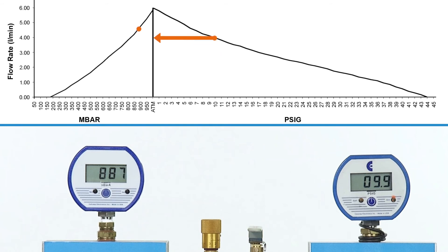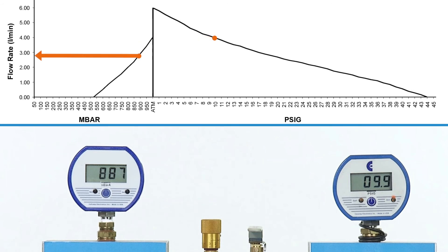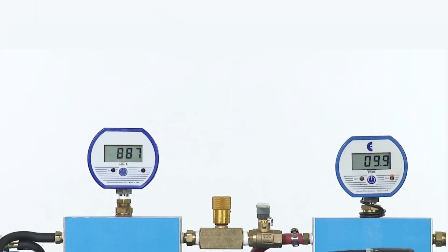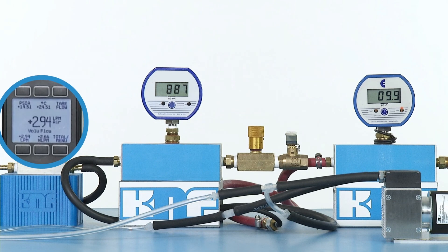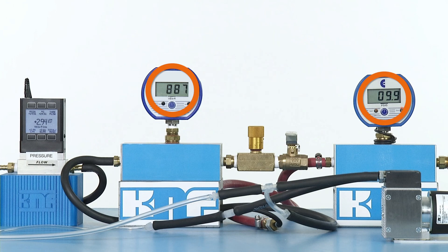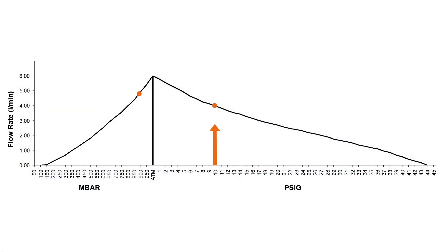Through a simple manipulation of the flow curve and chart using the two data points, the curve indicates an estimated flow rate of just under 3 liters per minute. A flow meter connected to the system confirms the estimate — 2.94, or approximately 3 liters per minute, is shown on the flow meter. To summarize, when both vacuum and pressure conditions are known, the flow curve of the pump can be used to estimate the flow rate.